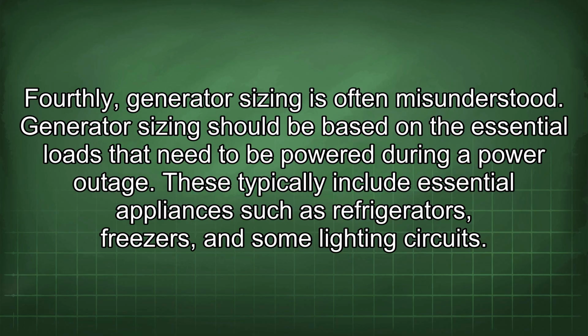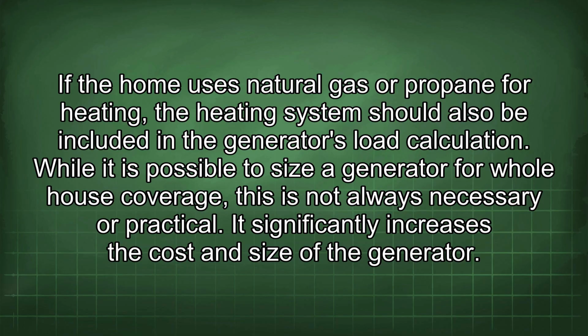Fourthly, generator sizing is often misunderstood. Generator sizing should be based on the essential loads that need to be powered during a power outage. These typically include essential appliances such as refrigerators, freezers, and some lighting circuits.